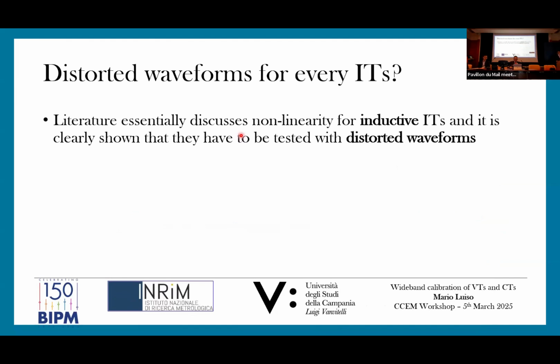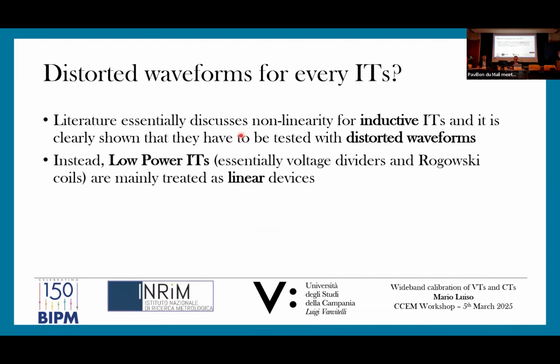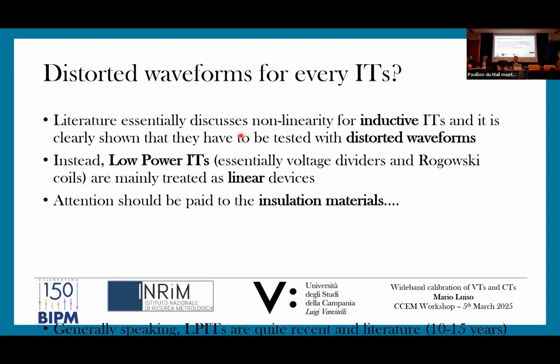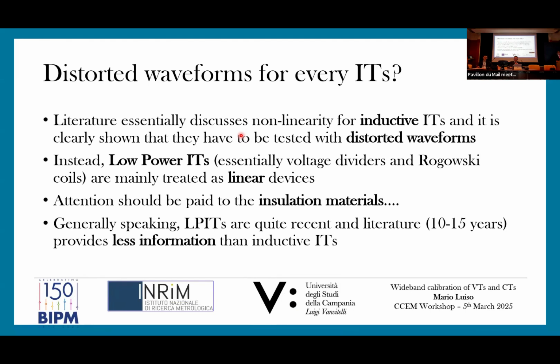But should we use distorted waveform for every instrument transformer? Well, literature essentially discusses the nonlinearity for inductive instrument transformers, and it is clearly shown that they have to be tested with distorted waveforms. Instead, in literature, low power instrument transformers, essentially dividers and Rogowski coils, are mainly treated as linear devices. But in my opinion, attention should be paid to the insulation material that can modify the behavior of the instrument transformer. Generally speaking, low-power instrument transformers are quite recent, and literature, about 10, 15 years, provides less information with respect to the inductive instrument transformers.